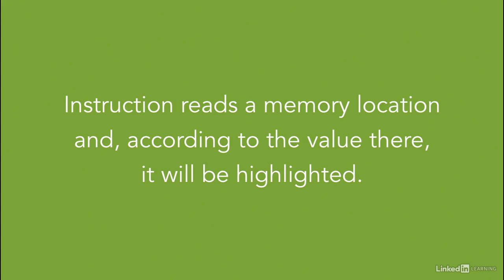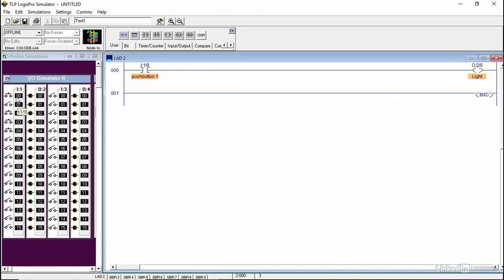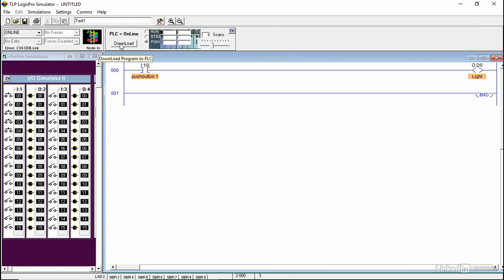Let's use the software to demo this simple example. In the simulation software, we have the push button connected to a light. I'm going to use the first push button with the address I1.0, and for the light, I'm going to use the first light with address O2.0. First, you need to go online, download the program to the PLC, and select run mode. Now the light is off because it's an XIC instruction. As soon as I press on the push button, the light will turn on.